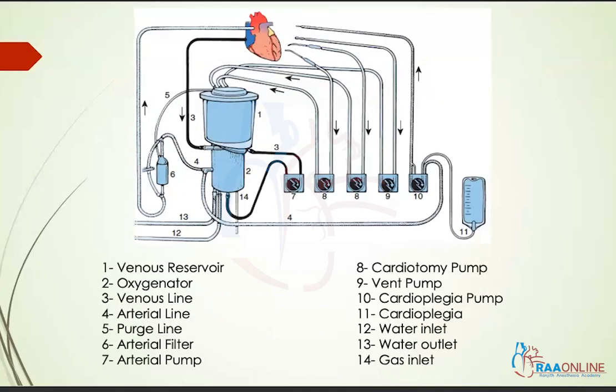This is the diagram of the cardiopulmonary bypass machine. The various components include the venous reservoir, and number two is the oxygenator. From the venous reservoir, the venous line goes on to the arterial pump, and from there it comes back to the oxygenator, where the blood gets oxygenated. Along with that, you have the cardiotomy pumps, the vent pumps, and the cardioplegia pump into which the cardioplegia is being delivered. Once all this is done, it is returned back to the patient through the artery.